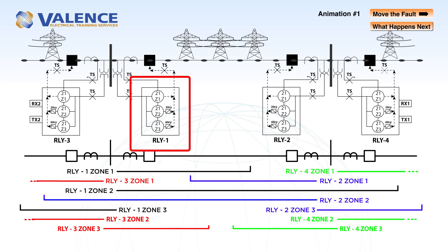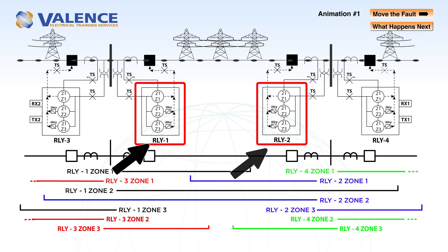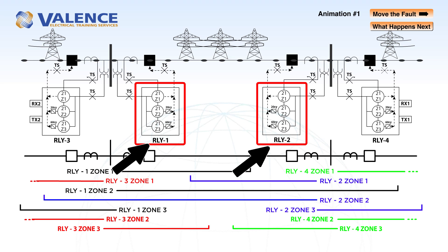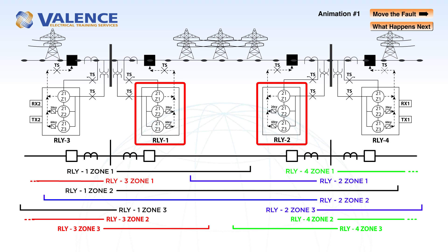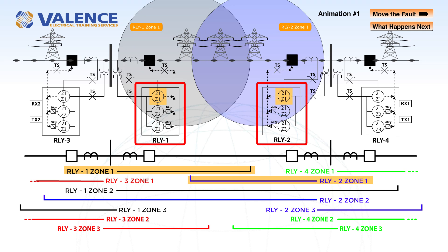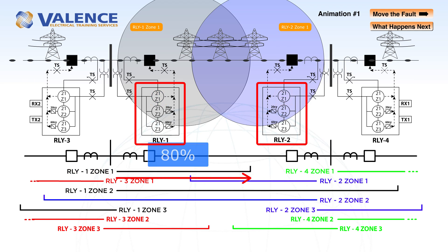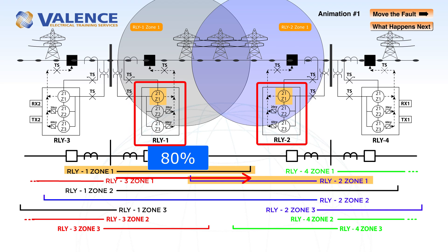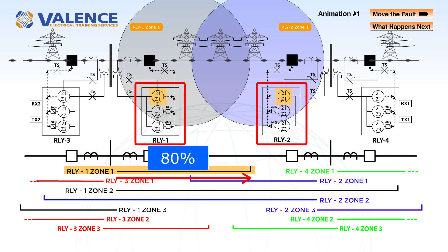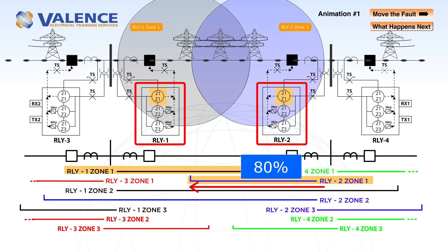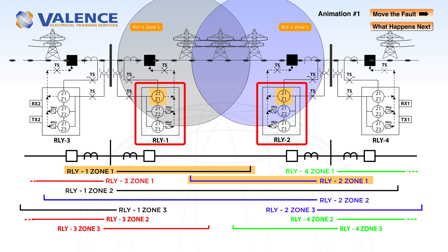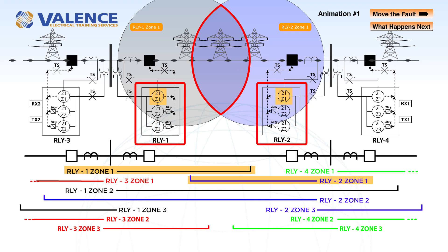We will be performing our tests on relay 1 and relay 2, which have identical protection settings used to detect faults on the transmission line between them. Both relays have zone 1 protection that is set to operate up to 80% of the line as shown by this black line for relay 1 and this blue line for relay 2. Zone 1 will pick up in each relay if the fault occurs above the lines indicating zone 1.